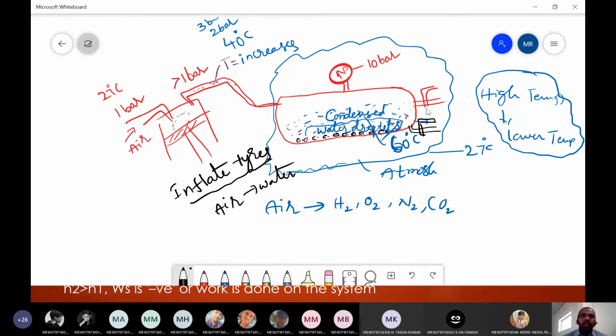Let us say today work is completed and tomorrow we are going to start the work fresh. At that time you need to operate this bottom valve. It is the bottommost point. Whatever water formed on the previous day due to condensation will have settled at the bottom, and if you open this valve, this water will escape outside the tank.